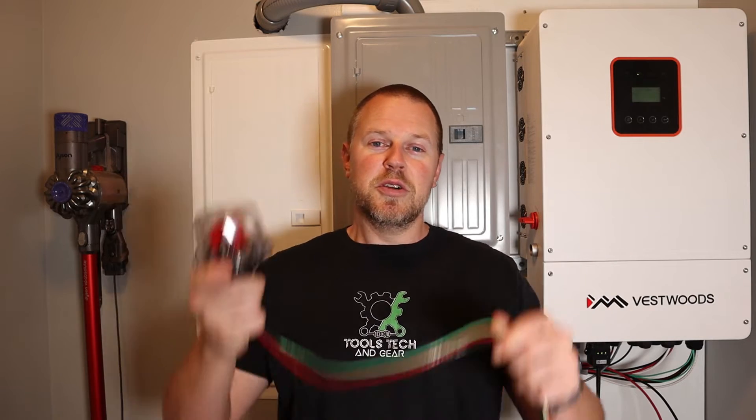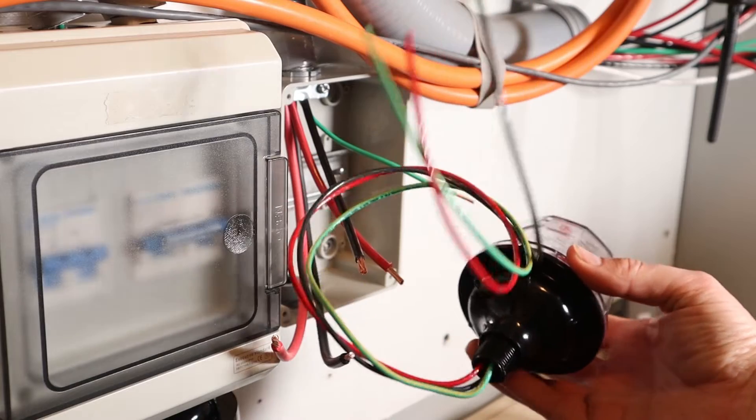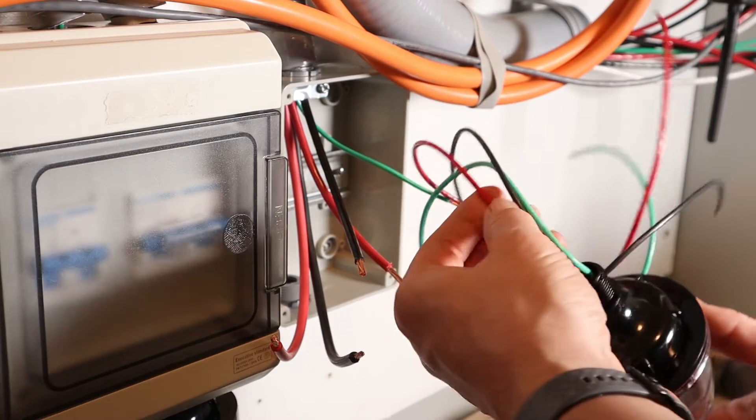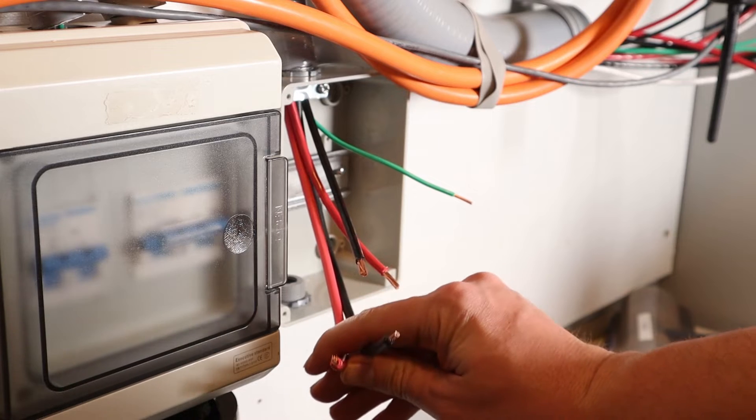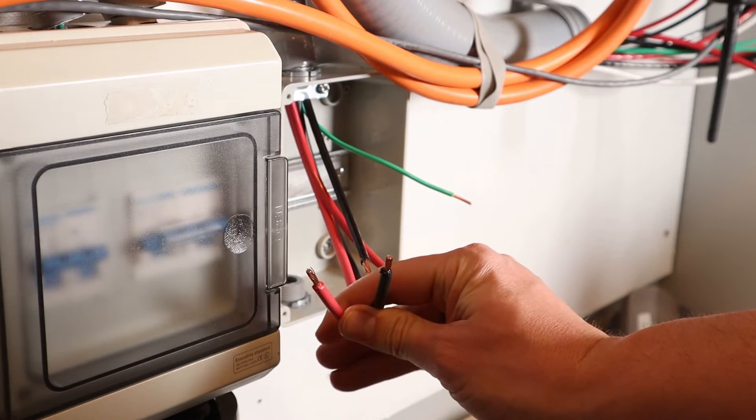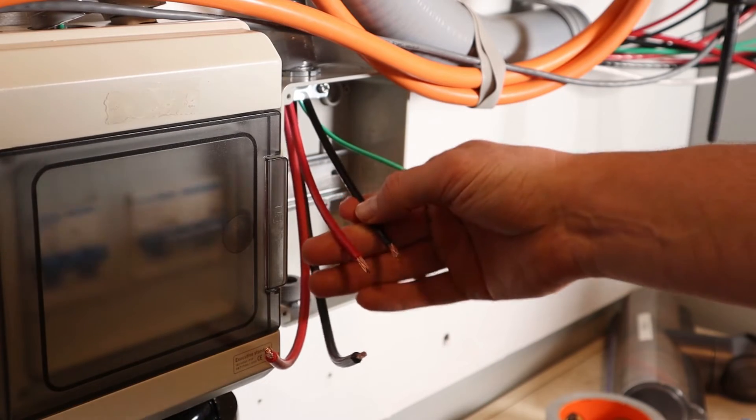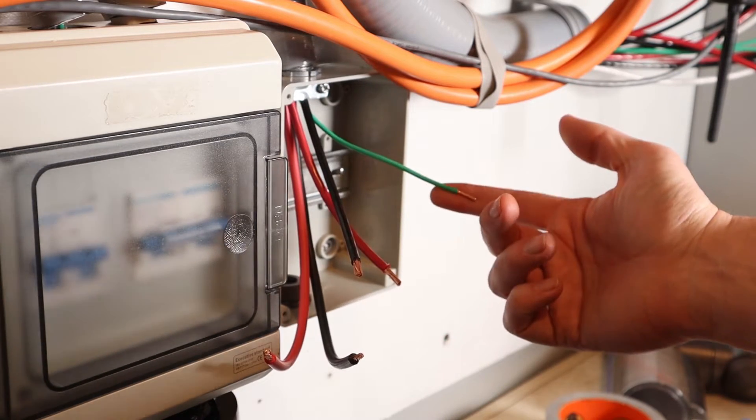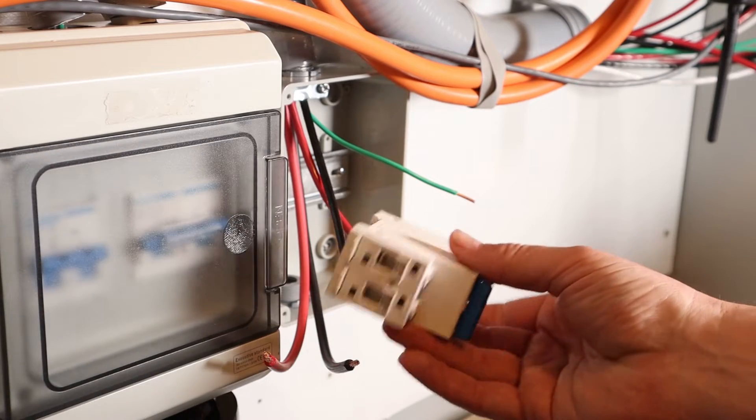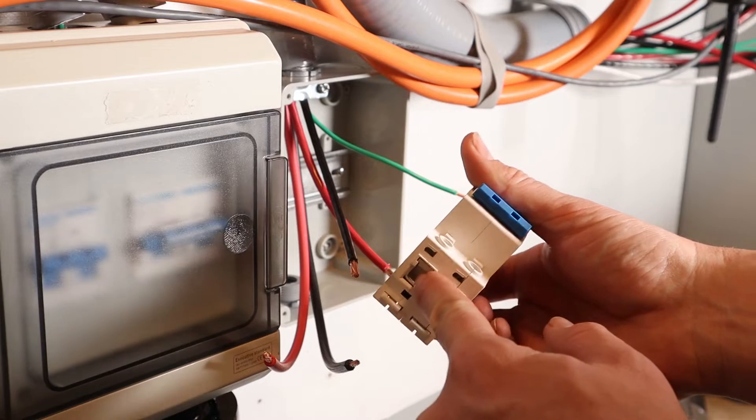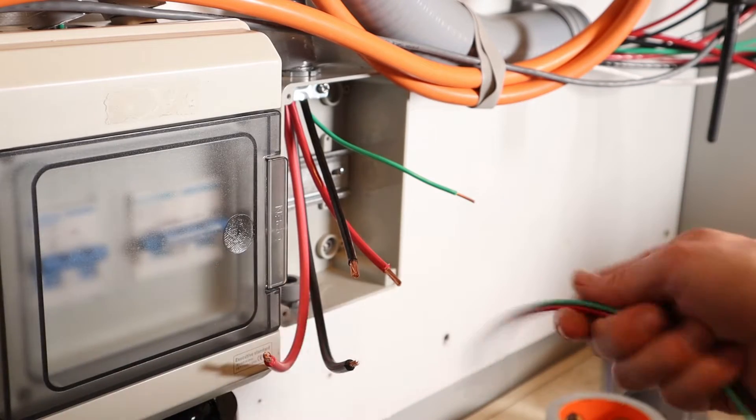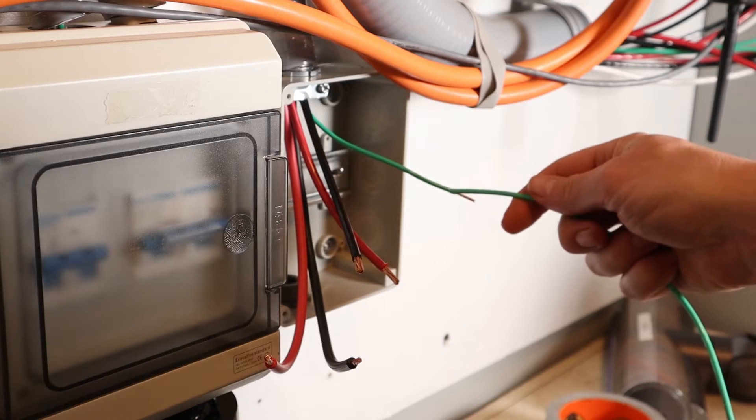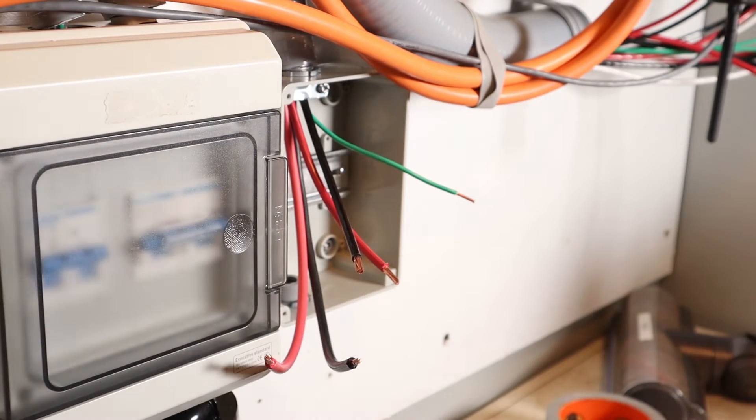In this video, I want to show you how I install the SPD. On the Midnight Solar SPD, there are three wires coming out of the bottom of the unit. The green is ground, the black is negative, and the red is the positive. Here I've got two wires coming in from my solar outside. Now they're not connected out, so I can work with them. And I have the two wires going to my inverter, which will have an MPPT charge controller. And over here, I have a single ground going to earth ground outside. This right here will go into the bottom of a breaker. So the red will go on this side, black will go on that side. And then up here is where we're going to be attaching these red and black right here, along with these as well. And then the green will be connected to the earth ground. That is how simple it is to get this connected.